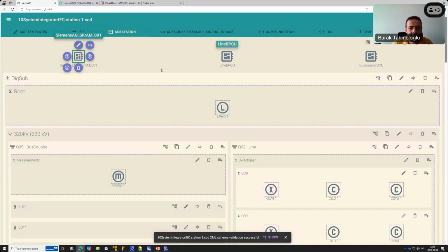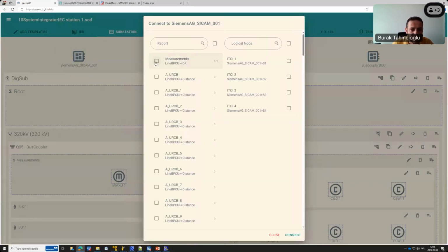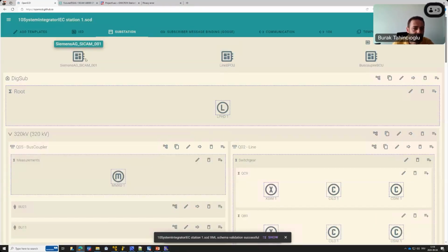Then I can assign the report to this client using the link button. I can say these measurements are reserved for the telecontrol interface of this logical node at access point S1. That way, I assign the report control block of this LineBPCU to the Siemens IED.